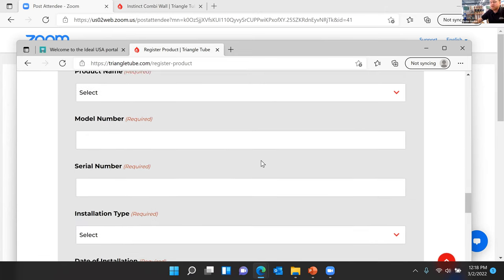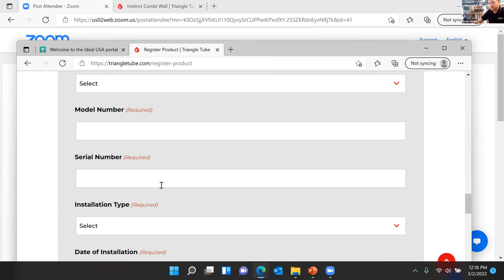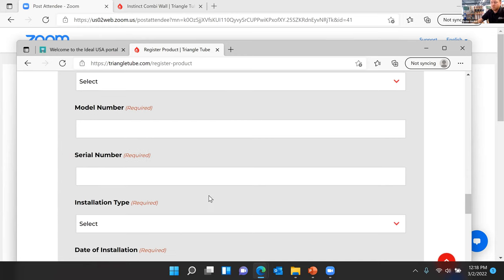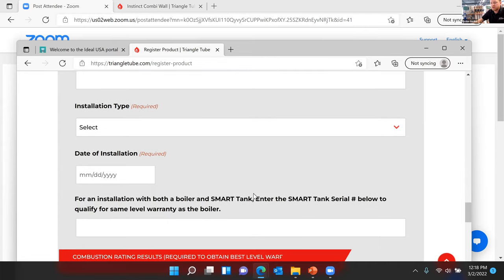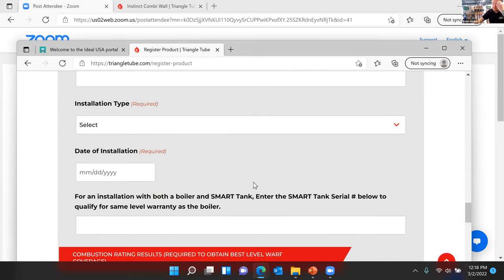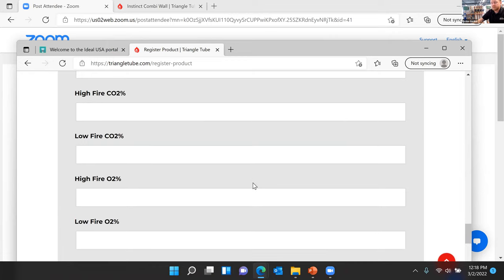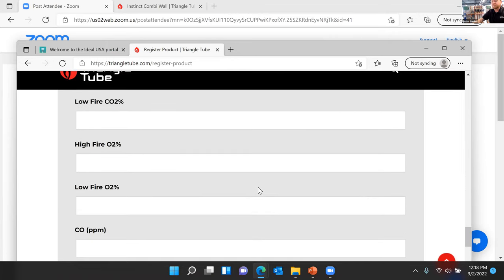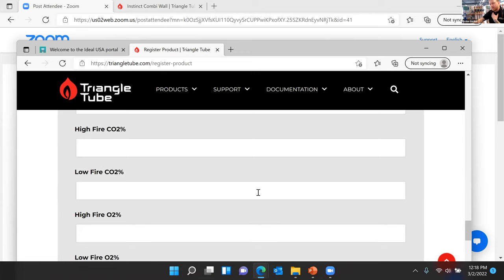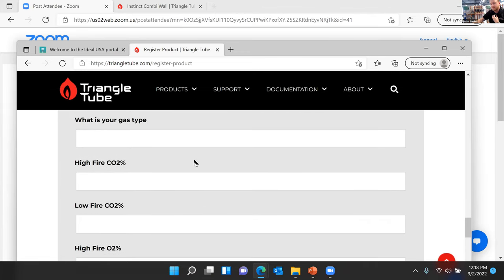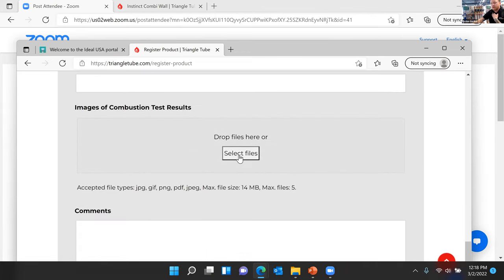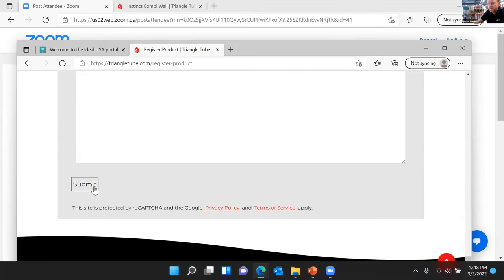Then you'll have your product info, serial number. That's the most important part for us. It tells us what the boiler model is, all the information, when it was made, and we can track everything. And then your combustion settings. Now, if you're on the job site and you have your analyzer, you don't technically need to fill in all this information. You just go in, take a picture of your analyzer in high fire, take a picture of it in low fire, making sure that your combustion settings are within our parameters in the manual, and then drop those pictures here and hit submit.